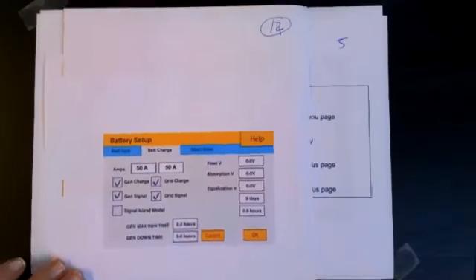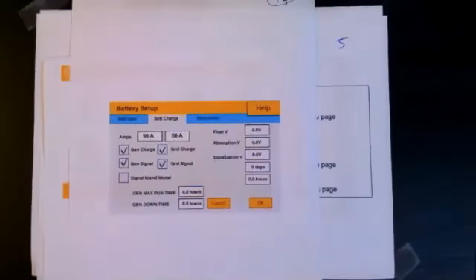I should have had another slide actually showing the battery type, but I haven't. I'm sorry, I didn't prepare it today. So the battery discharge is what they call the C rating of a battery. The C rating is something you need to calculate. If the battery is a 100 ampere hour battery, 100 ampere hour, 48 volt would be a 4.8 kilowatt hour battery, but this 100 ampere hour would relate to the C rating. So if the C rating is 0.5, that means you can draw 50 amps charge, discharge. You can't go more than that.